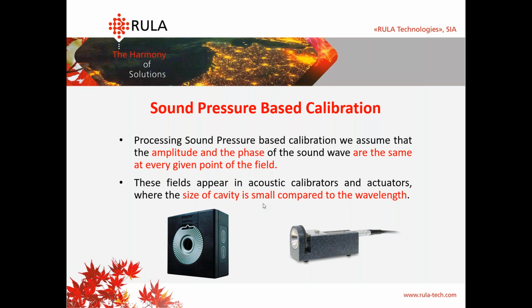After that, we go to sound pressure-based calibration. This principle is based on the idea that the amplitude and the phase of the sound wave are the same at every given point of the field. That means we have a really small space, like in the actuator or sound acoustic calibrator. In that case, we can think that the amplitude and phase of the sound will be the same at every point of this chamber.